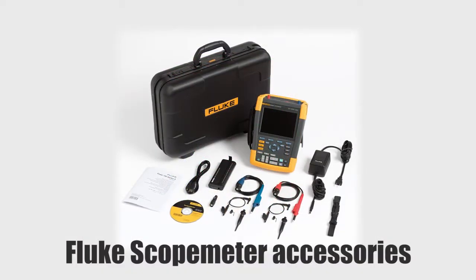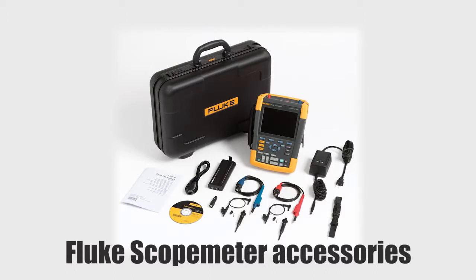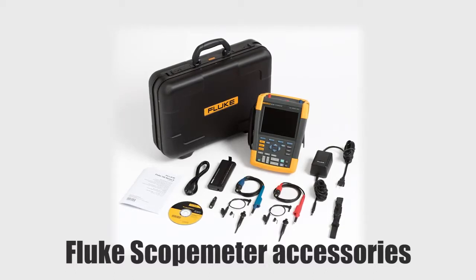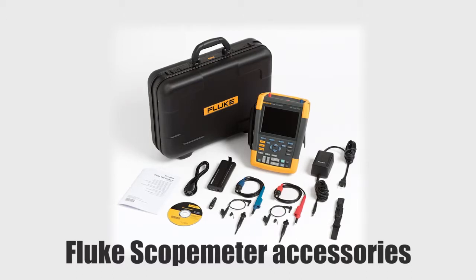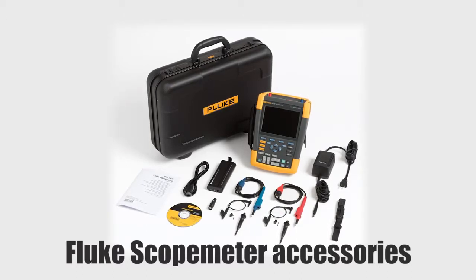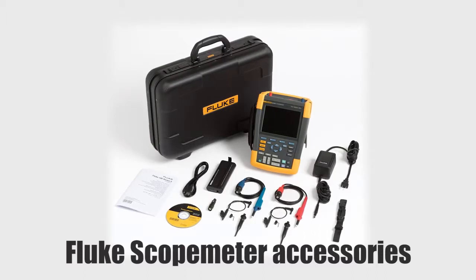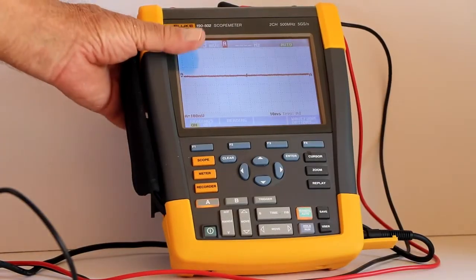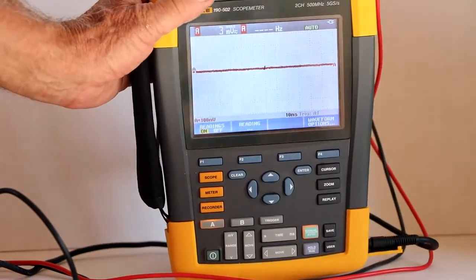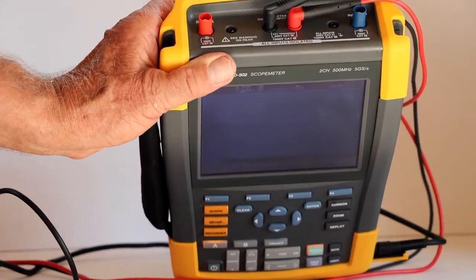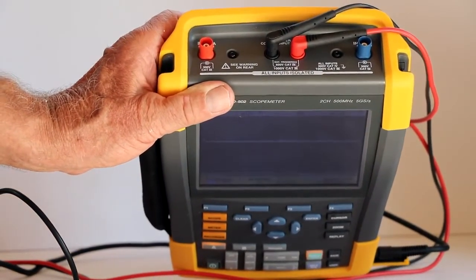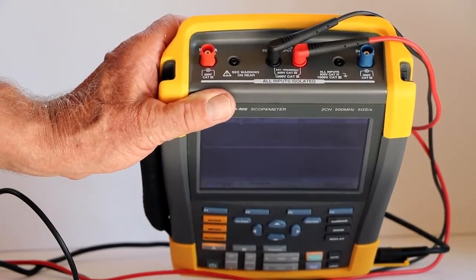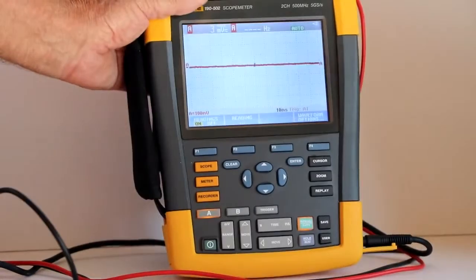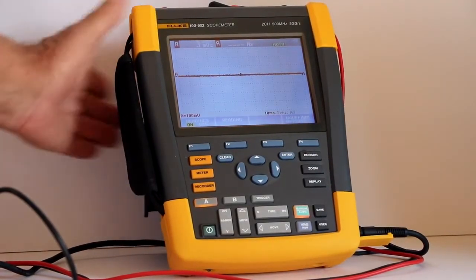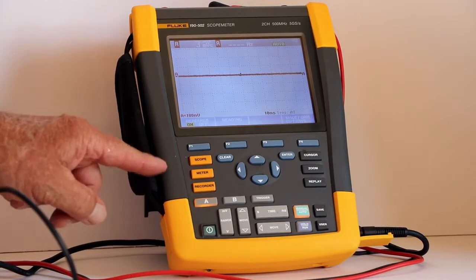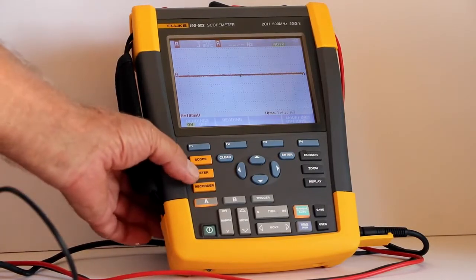The Fluke 190-502 ScopeMeter, as its name implies, performs the dual function of depicting waveforms like a traditional oscilloscope and also taking voltage, current, and resistance measurements in the manner of a far simpler multimeter. On the top panel, this two-channel instrument has two oscilloscope analog channel inputs, one at either side, and between them a pair of banana jacks that will accept ordinary multimeter probes. To choose between modes, simply press Scope or Meter. To illustrate, we'll press Meter and take some measurements.